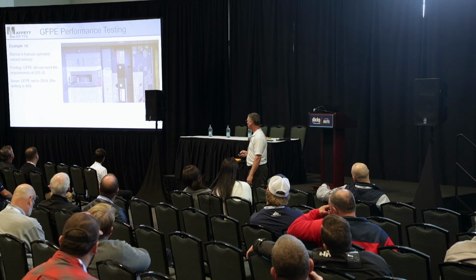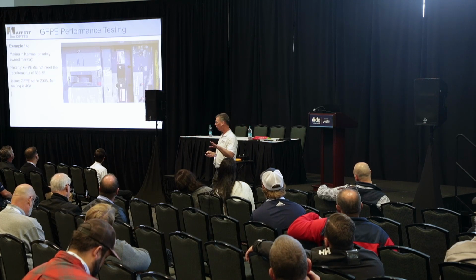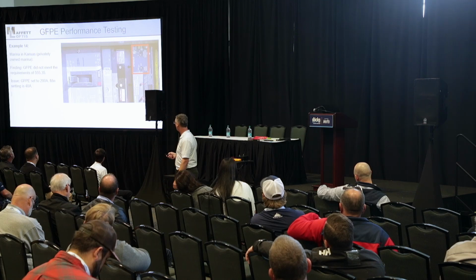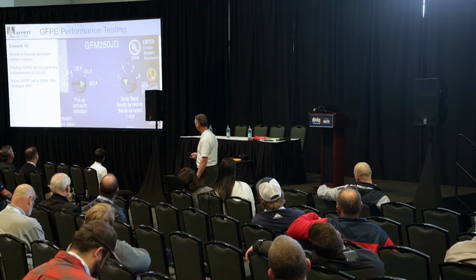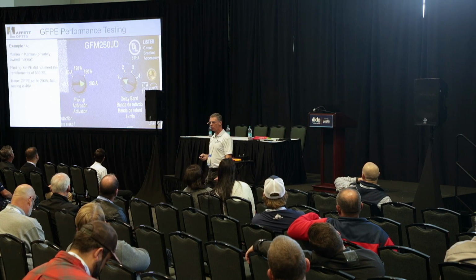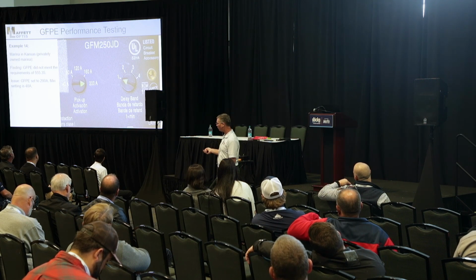That is a GFPE device with a shunt trip breaker. But what is the maximum level I've been saying on a feeder, how many milliamps? 100 milliamps, okay? If you look at this, look at that ground fault monitoring system, there it is, that's the setting. Is that anywhere close to the 100 milliamps? No, the minimum is 40 amps. That's 40,000 milliamps, not even close to what we needed.